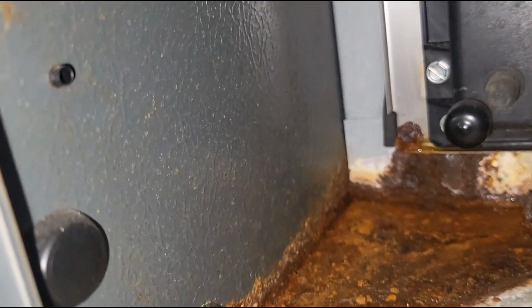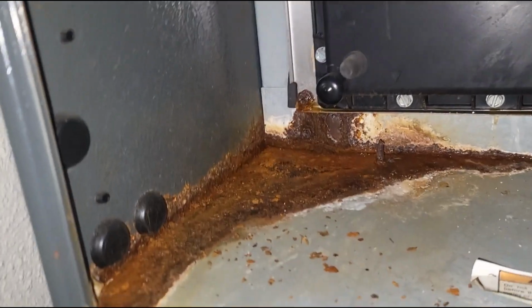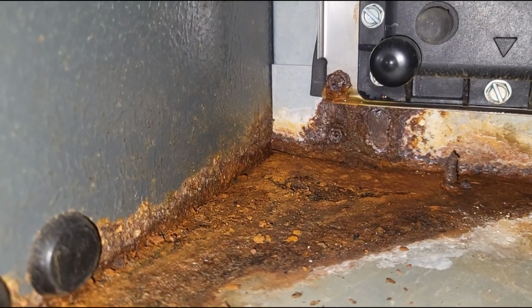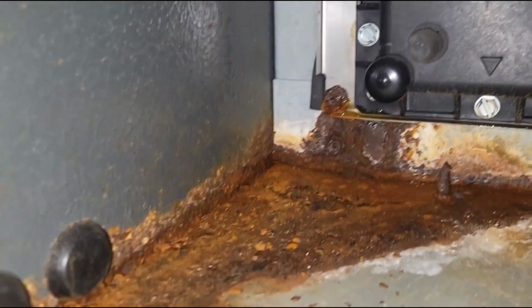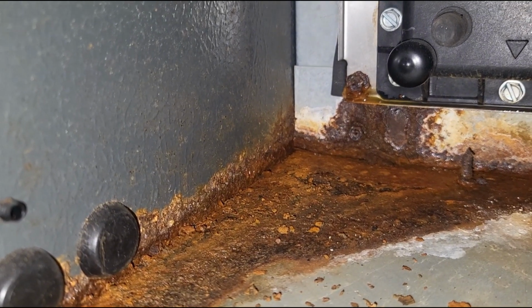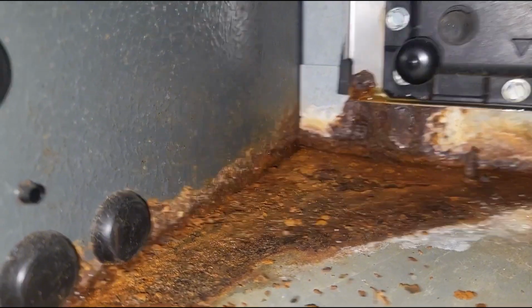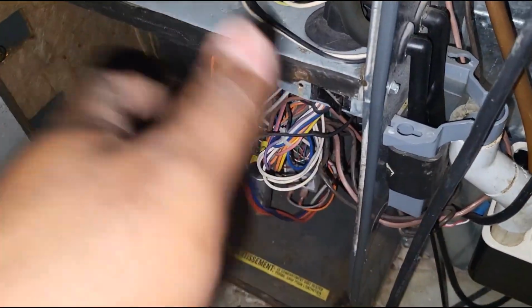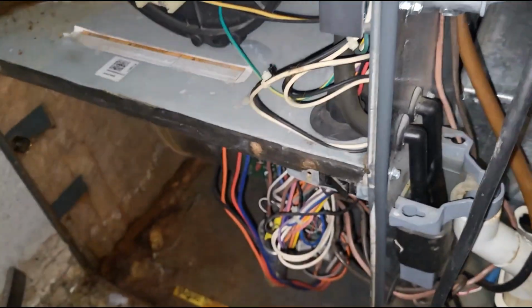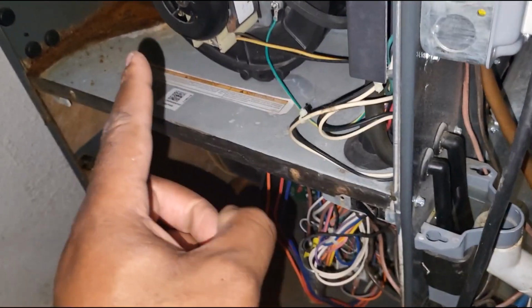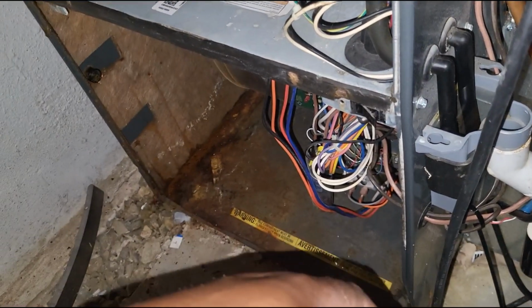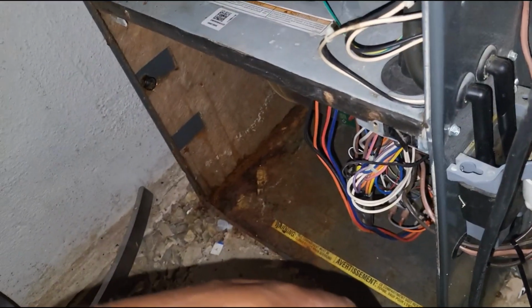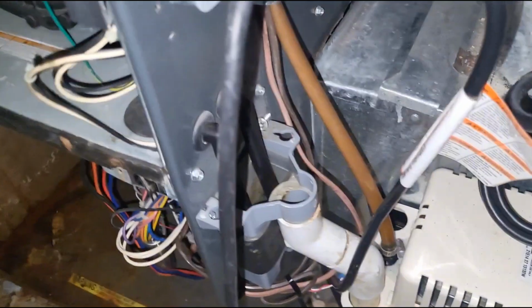And guys, this isn't coming from the collection box, this is actually the front plate of the heat exchanger. So even if we replace this collection box, I'm not sure if this is going to go away. Right now it's not actively leaking, but we don't want this to come back and potentially cause issues with the circuit board, all the electrical components, keeping in mind this is a 90% unit. If that heat exchanger isn't properly draining, that could open up one of our pressure switches and cause this unit not to work. So for sure we'll notate that.